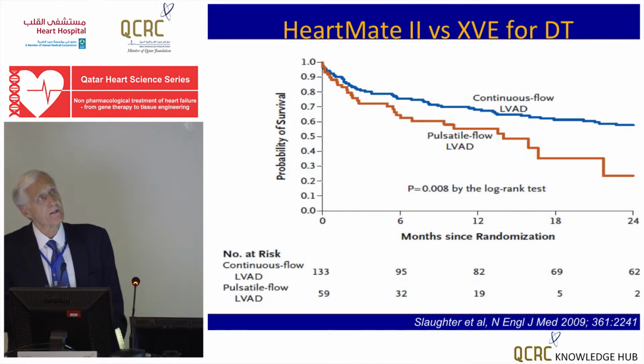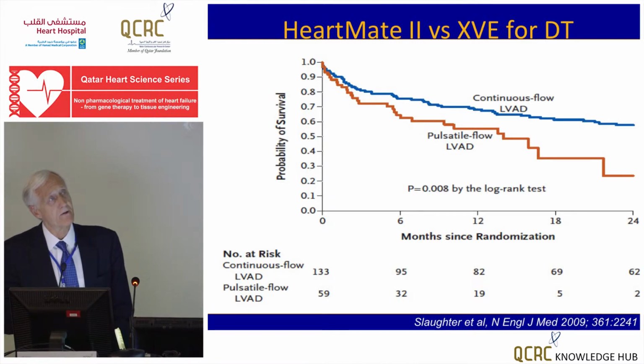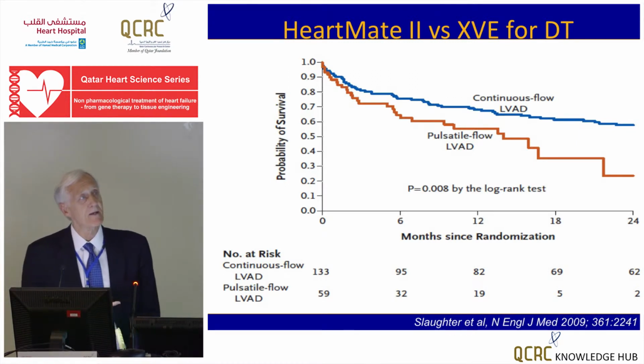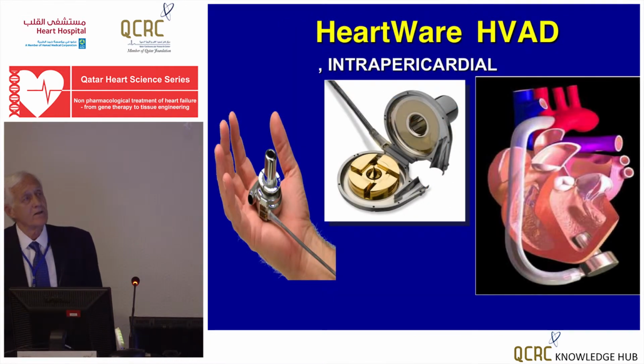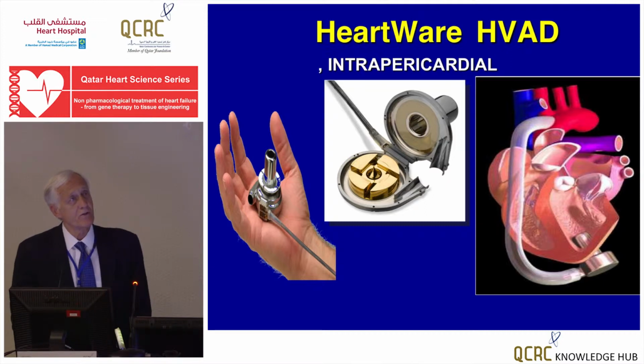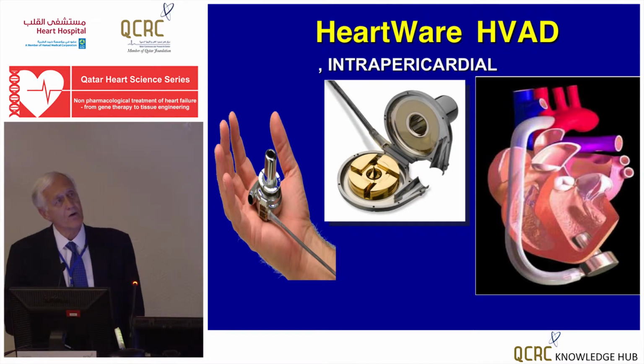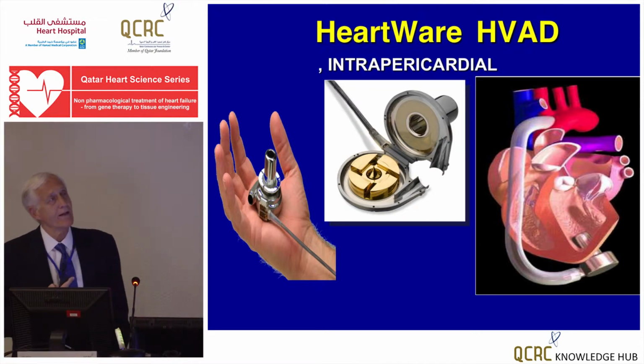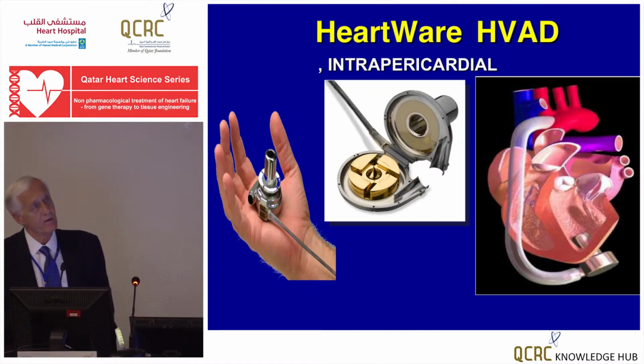We saw it applied for destination therapy as well, and began to see probably about a 10% difference in overall survival. But when we went head-to-head of the original pulsatile flow versus the continuous flow, this data made it very clear, and within a year and a half of this publication, the production of this device, which had been the centerpiece, was basically abandoned. We moved from still a pocket requirement for the original iteration of the continuous flow pump to now a completely contained within the mediastinum and within the pericardium. And this apical implant, you can see the motor and rotor now requires no pocket, and really revolutionized the field even further. And I think you begin to see how much miniaturization these pumps have, and change from an axial to a centrifugal flow and magnetic levitation, so the blood contact and trauma to the blood was reduced rather dramatically.